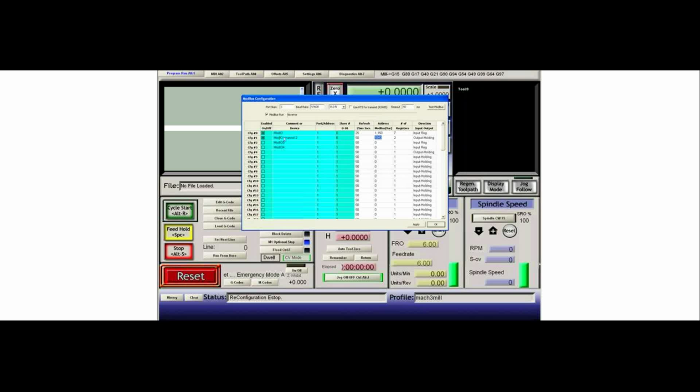So here we have, basically, I'm doing 2 operations. Every 25 milliseconds, I'm sending 7 registers from the PLC, or Mod I/O in this case, into configuration 0. And every 50 milliseconds, I'm sending 2 registers from configuration 1 to the Mod I/O on address 1040. So using this screen, you can set up to 64 different configurations of Modbus data. And each configuration has 127 bytes of data, or words of data maximum, that you can use.